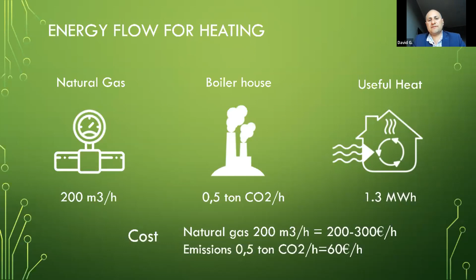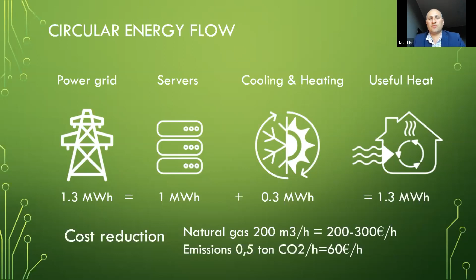But if we choose circular economy, in that case we will get the same 1.3 megawatt hours from the power grid. We provide 1 megawatt for the servers, but we can use a heat pump which provides cooling for the servers and heating for useful applications. In that case, we get 1.3 megawatt hours of heat and don't need to burn natural gas, saving on gas consumption and CO2 emissions. This is just an example of how it can be not only decarbonized but also financially more attractive, for both the heat provider and the data center.